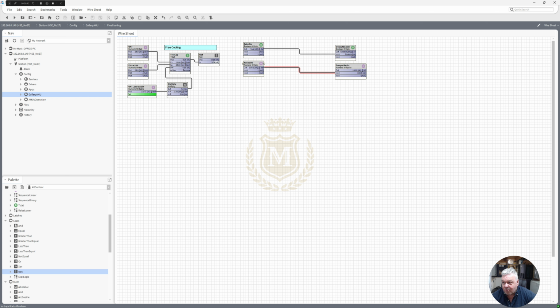And then this here we want to break into this. So if it's on this output here, how I would break into that is I would take that false, so I would put an AND gate in here, and put that there, take that out of there, put that into there, and rename free cooling enable. And I would take that into there, so I would disable the recirc. That's how I would disable the recirc.